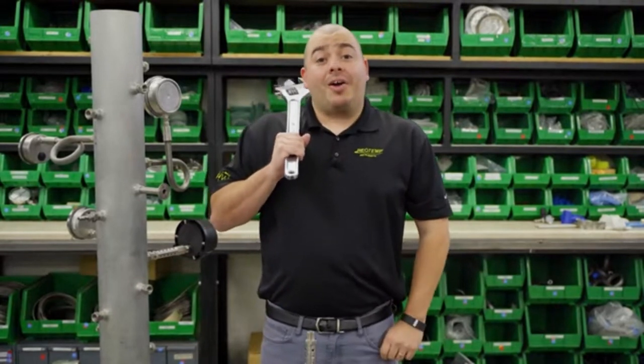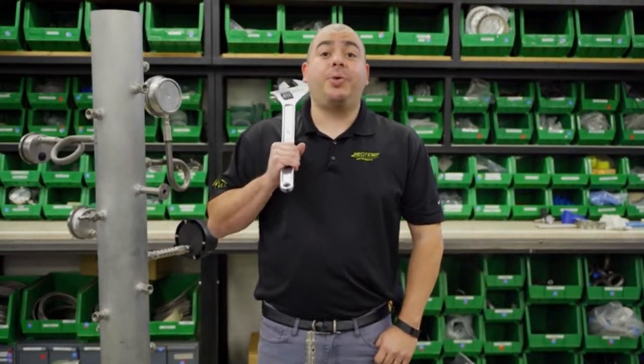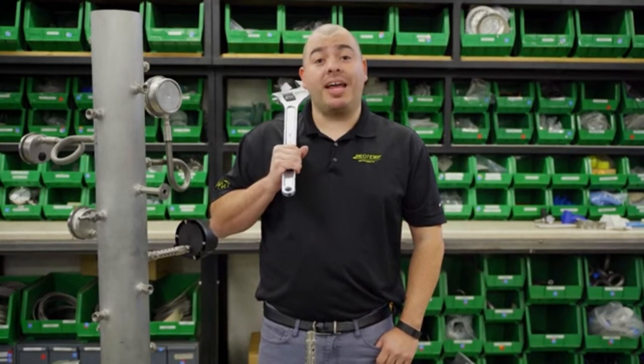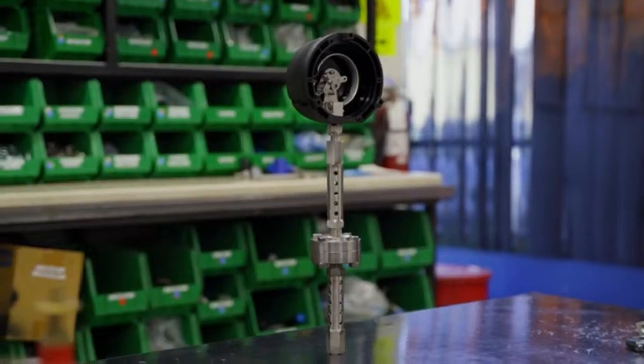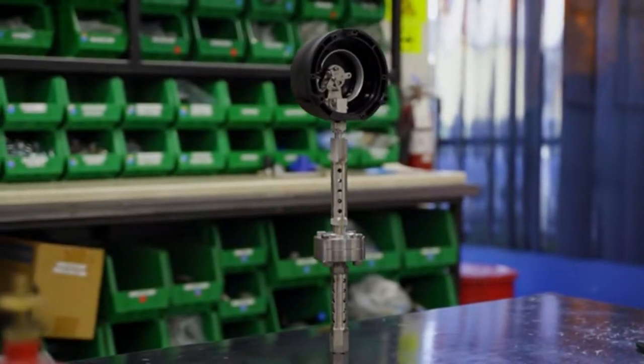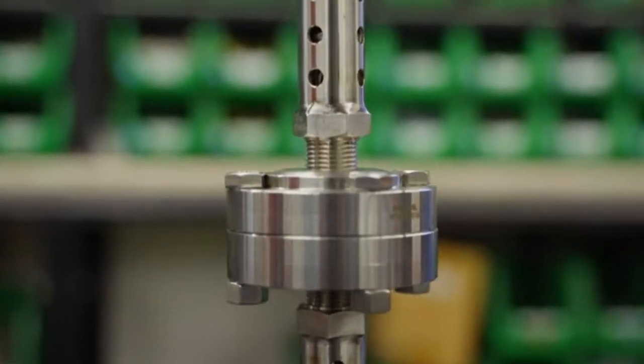You can add a cooling tower below the diaphragm seal to cool the gas prior to it coming in contact with the diaphragm surface. It isn't uncommon for an assembly to have 2 cooling towers, one below the seal and one above.